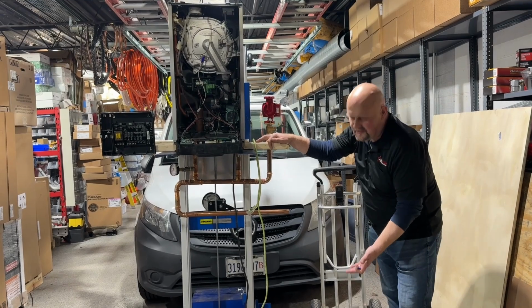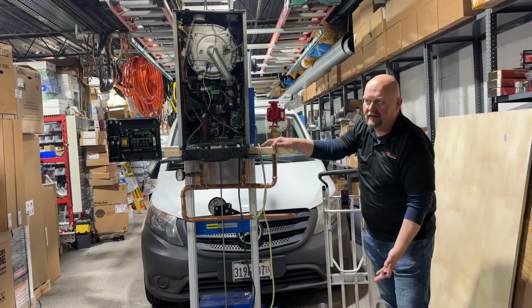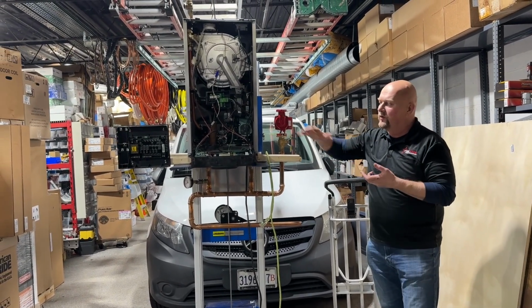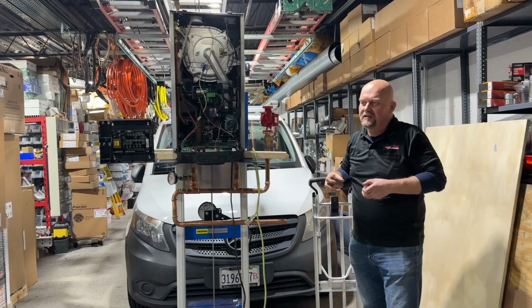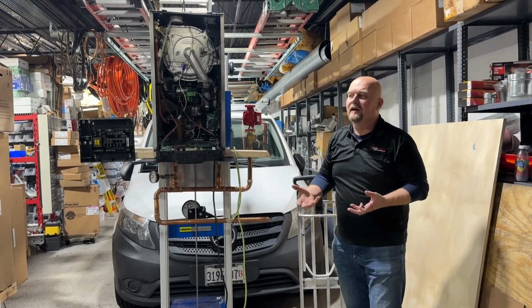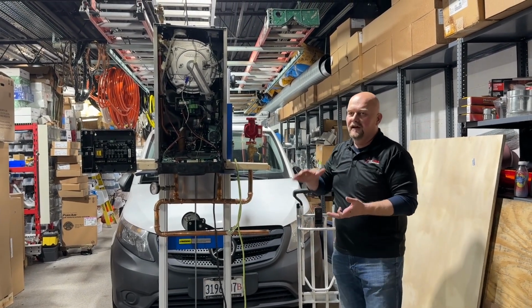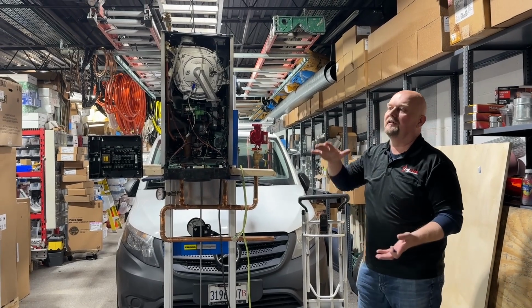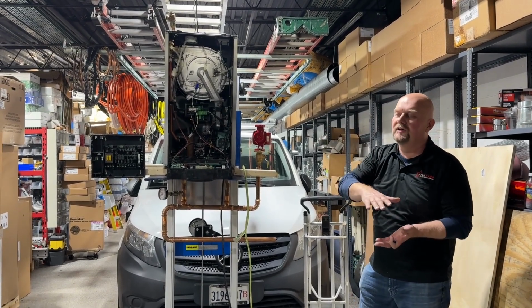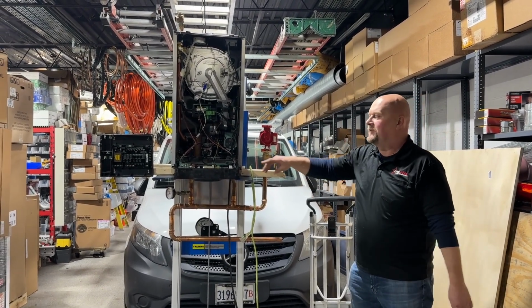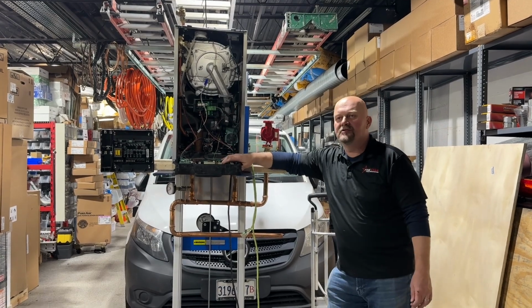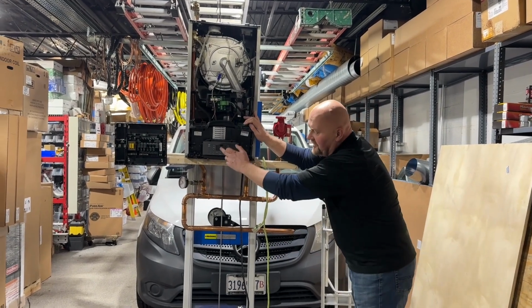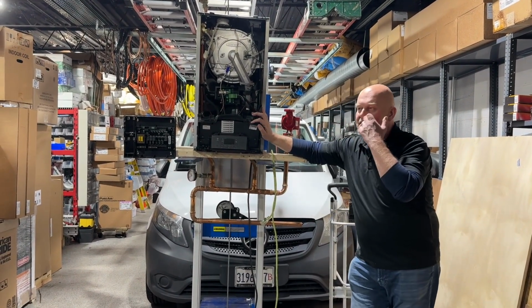And this tank is half water, half air, with a bladder inside. Once this water starts getting hotter, it'll start pressing against the air side of the tank, and the air will give a little. It'll allow the membrane to move down to equalize the pressure. Whenever you guys see these boilers running, you're always going to see some of them have the pressure on the display, and you're going to see it climbing.